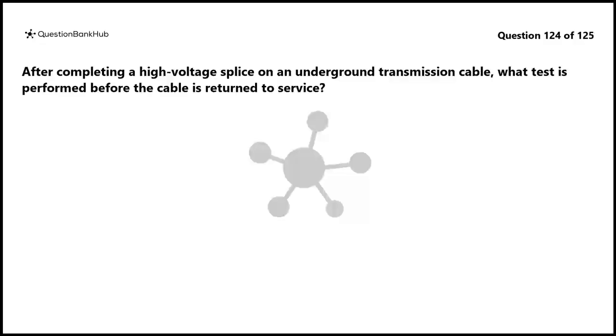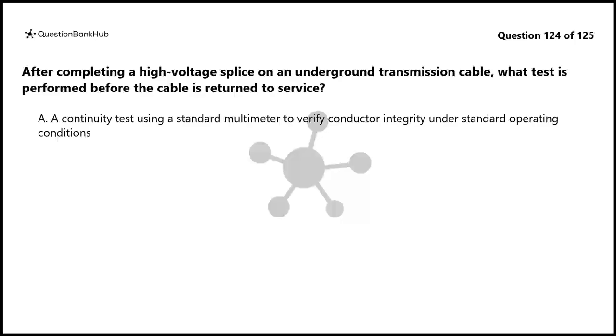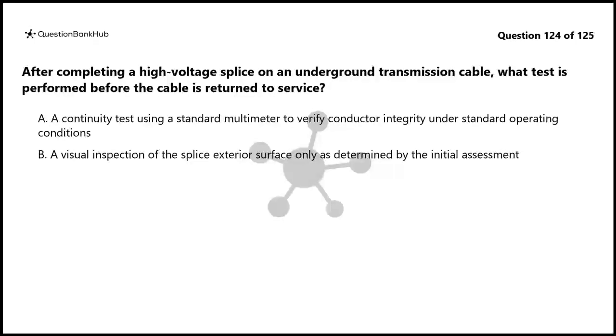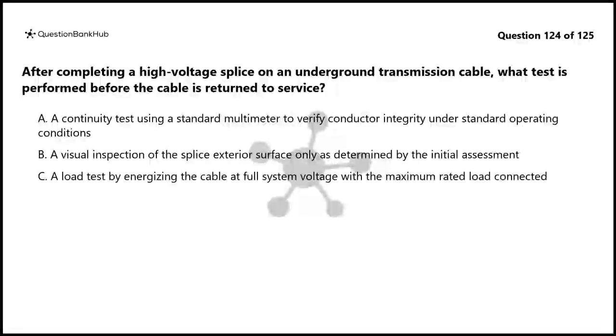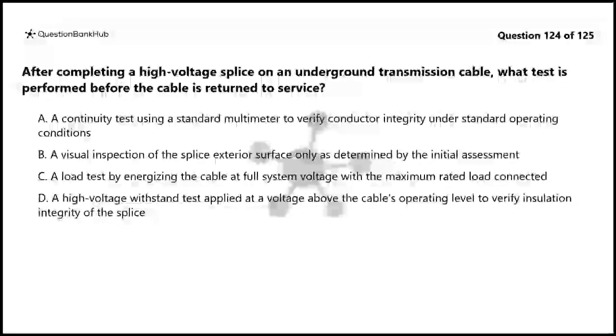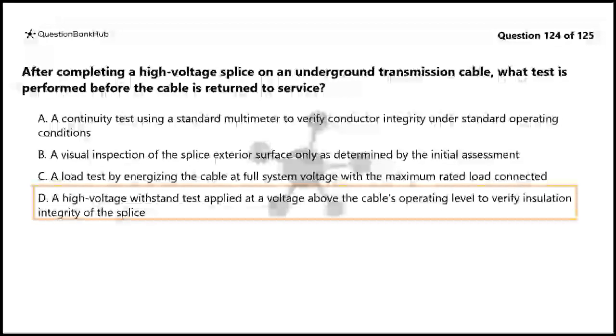Question 124. After completing a high-voltage splice on an underground transmission cable, what test is performed before the cable is returned to service? A. A continuity test using a standard multimeter to verify conductor integrity under standard operating conditions. B. A visual inspection of the splice exterior surface only as determined by the initial assessment. C. A load test by energizing the cable at full system voltage with the maximum rated load connected. D. A high voltage withstand test applied at a voltage above the cable's operating level to verify insulation integrity of the splice. The correct answer is D.